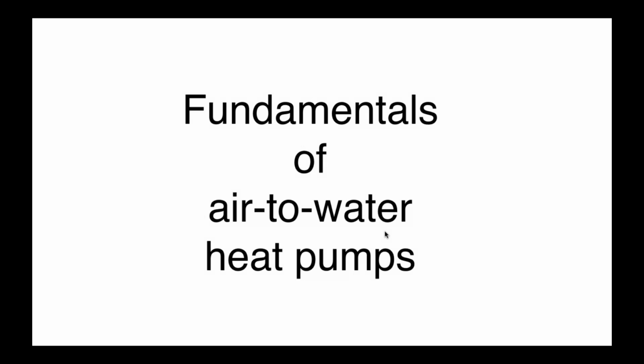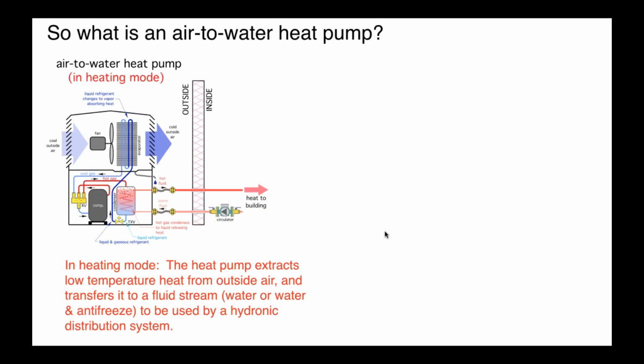Now, let's get right into fundamentals of air-to-water heat pumps. Most heat pumps today are reversible, meaning they can act as a heating machine or as a cooling machine. And that is the case with air-to-water. So in heating mode operation, wintertime operation, we have basically a standard four-function refrigeration system. We have an evaporator, a compressor, a condenser, and a thermal expansion valve. They are specifically configured in this case so that in the winter, we're absorbing heat.